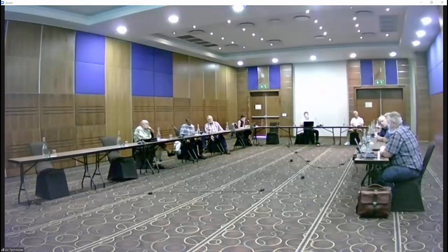When we do the assessment of a consultation room and you simply open a window, then the number of air changes per hour jumps to 60 to 70 air changes per hour. So it's an order of magnitude larger ventilation volume that you get simply by opening up a window. People should not underestimate the importance of making sure that windows are open.